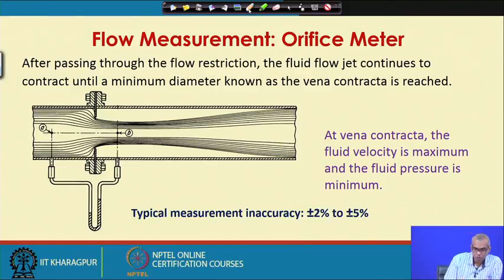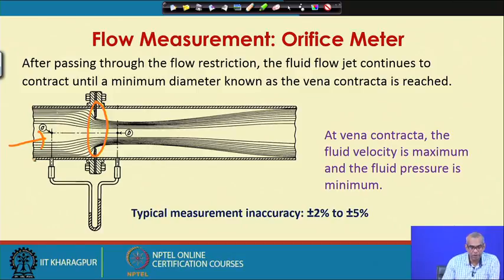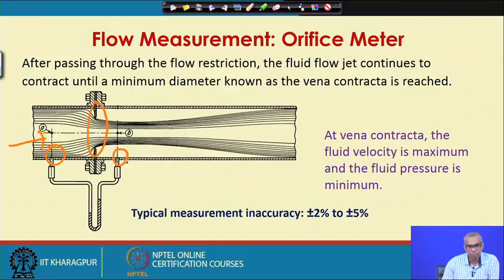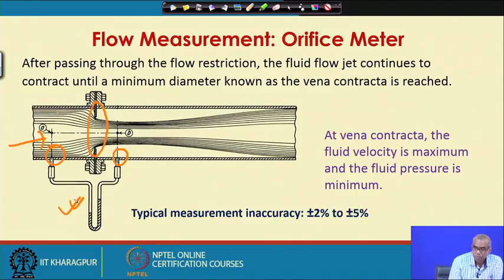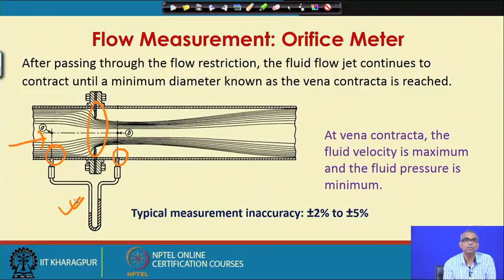The schematic shows an orifice plate where the fluid flows in one direction. There are two pressure tappings for measurement of pressure — one on the upstream and one on the downstream. A manometer or DP cell is attached for measurement of differential pressure. When the fluid passes through the flow restriction, the fluid flow jet continues to contract until a minimum diameter known as the vena contracta is reached.